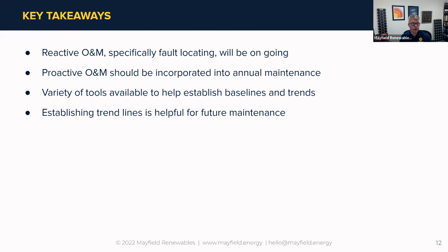for others as well. And then I know we've said it time and time again, but establishing trend lines is important for future maintenance. So with all of these aspects, the insulation resistance testing, the DLRO, voltage measurements, all those things, you can create logs, you can create trend lines. And so you can be looking at your system over the course of time to better understand how it is operating, and maybe where it's going, and be able to get ahead of some things and do some maintenance that you see coming ahead of time.